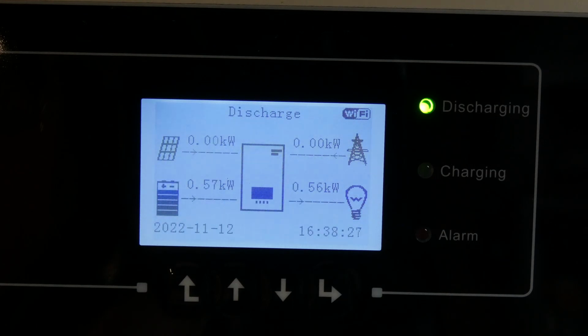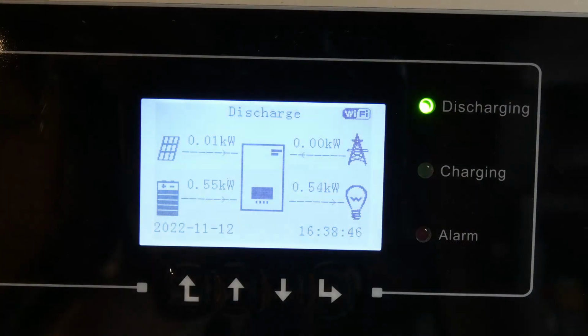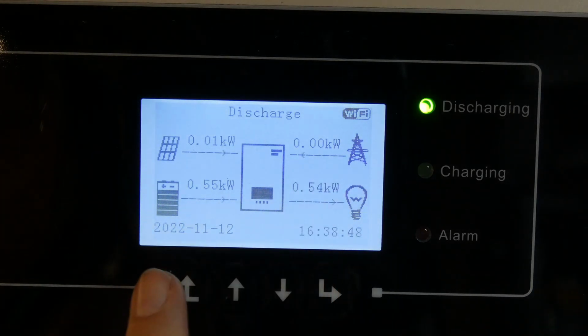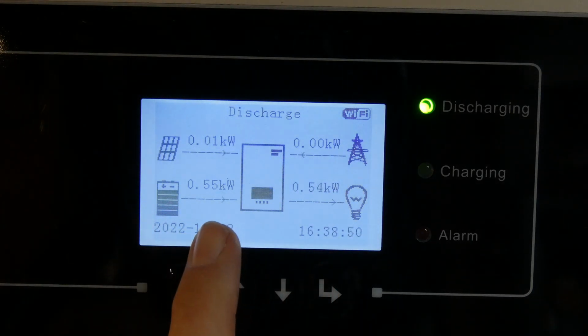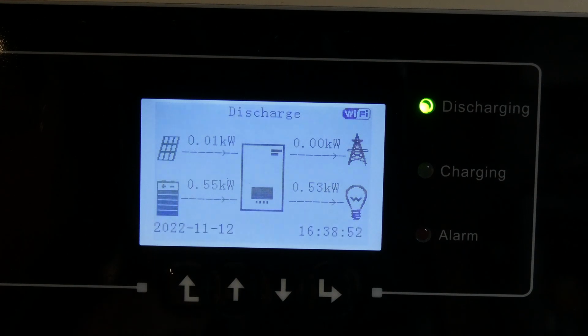So after a quick bit of research, I found out what the problem was. Because I hadn't plugged in a temperature sensor into one of the modules, the code in the DIYBMS was clever enough to not let the inverter discharge or charge while that was going on. So I've plugged the temperature sensor in, and as you can see from the screen, I'm now pulling 0 from the grid, even though it's dark outside, and the battery is now supplying 550 watts.